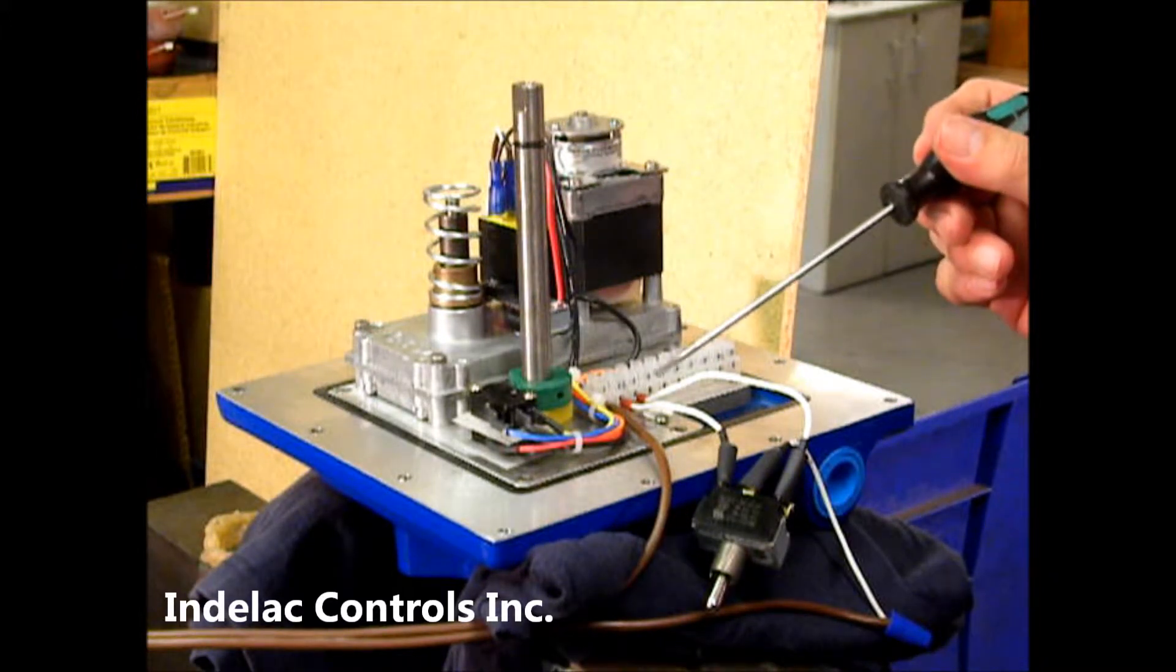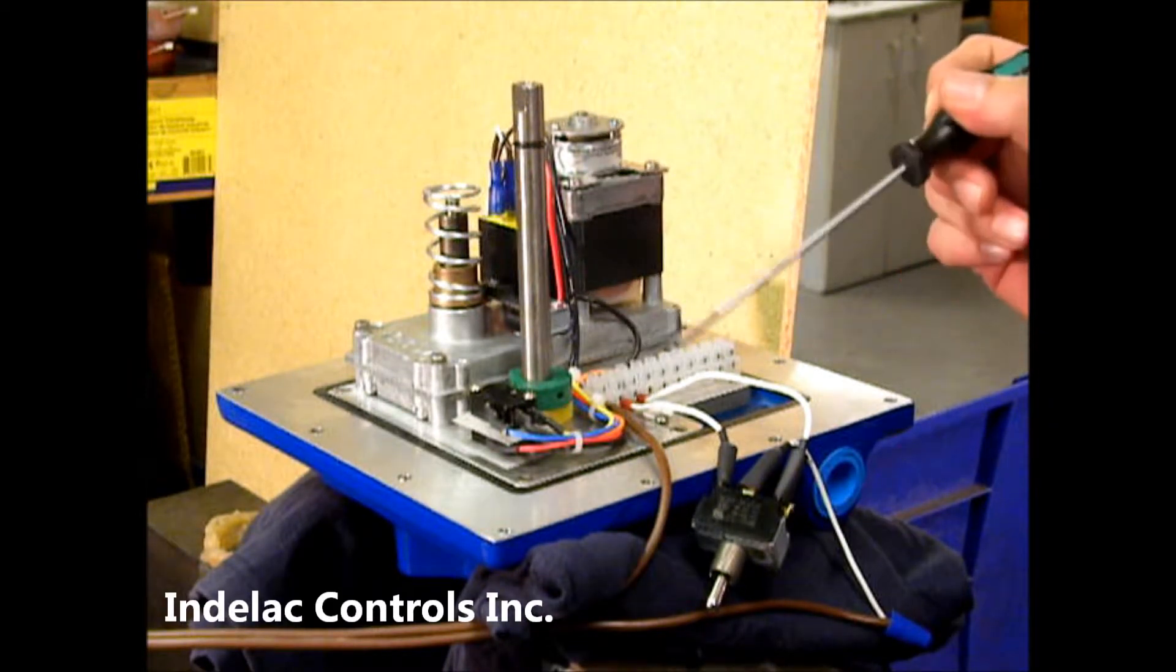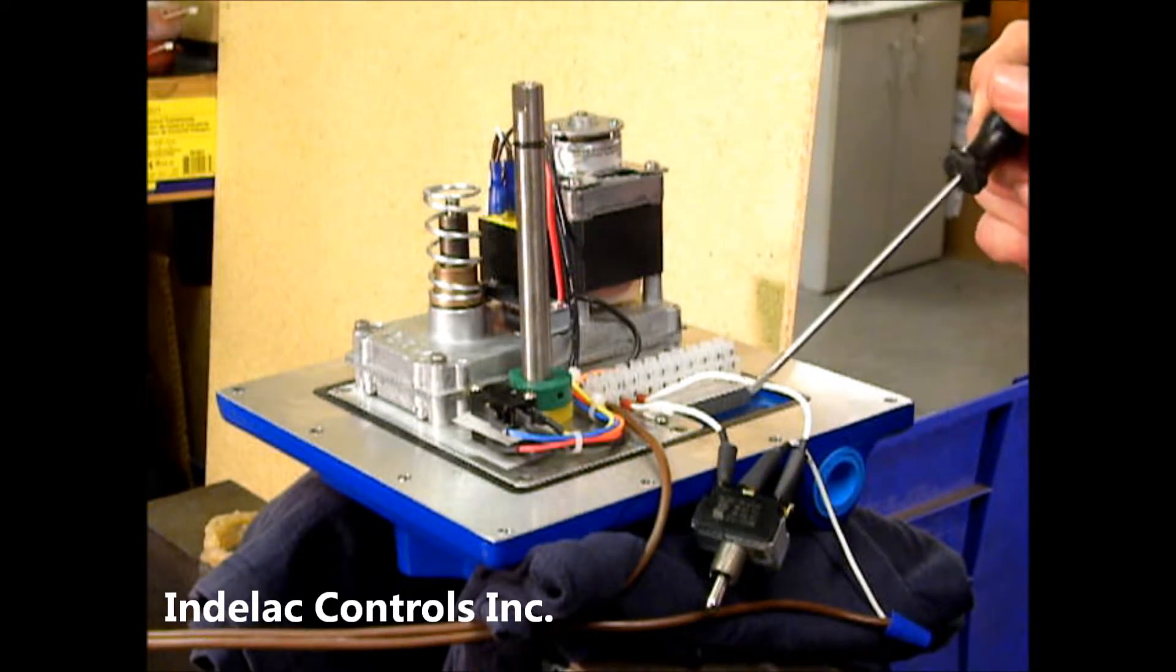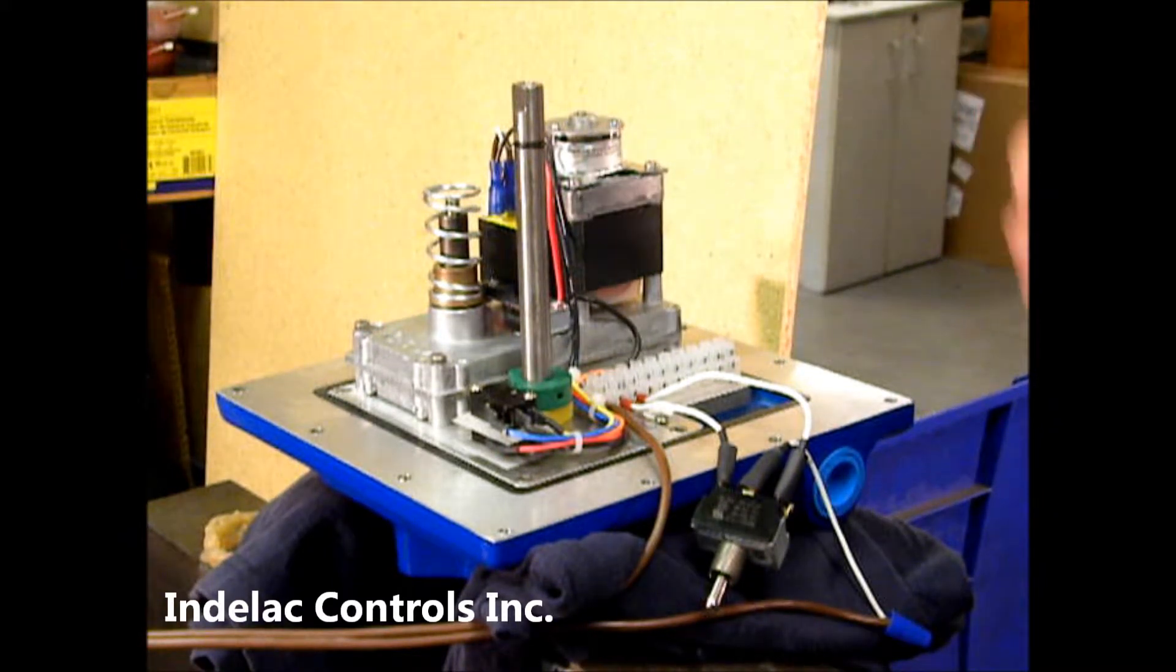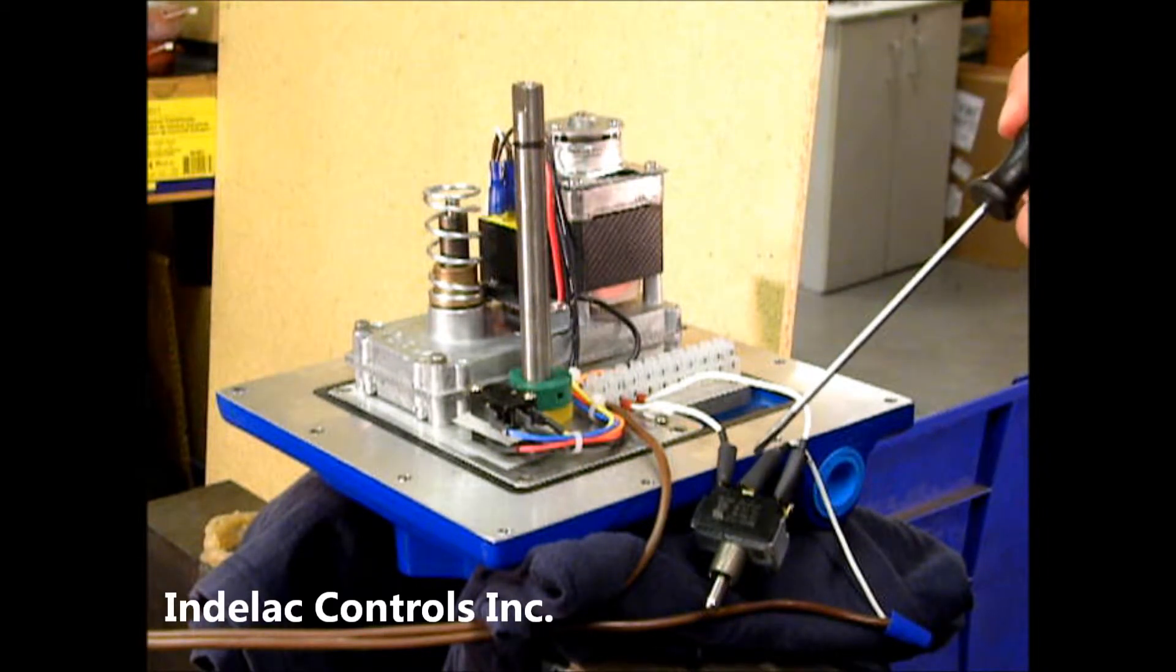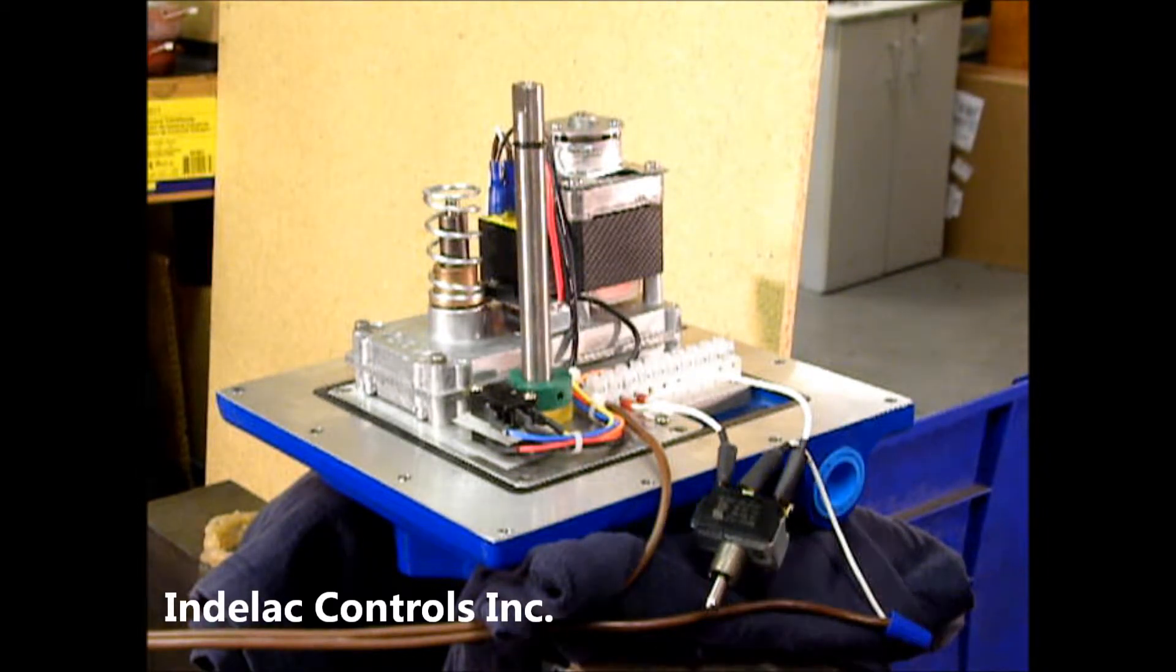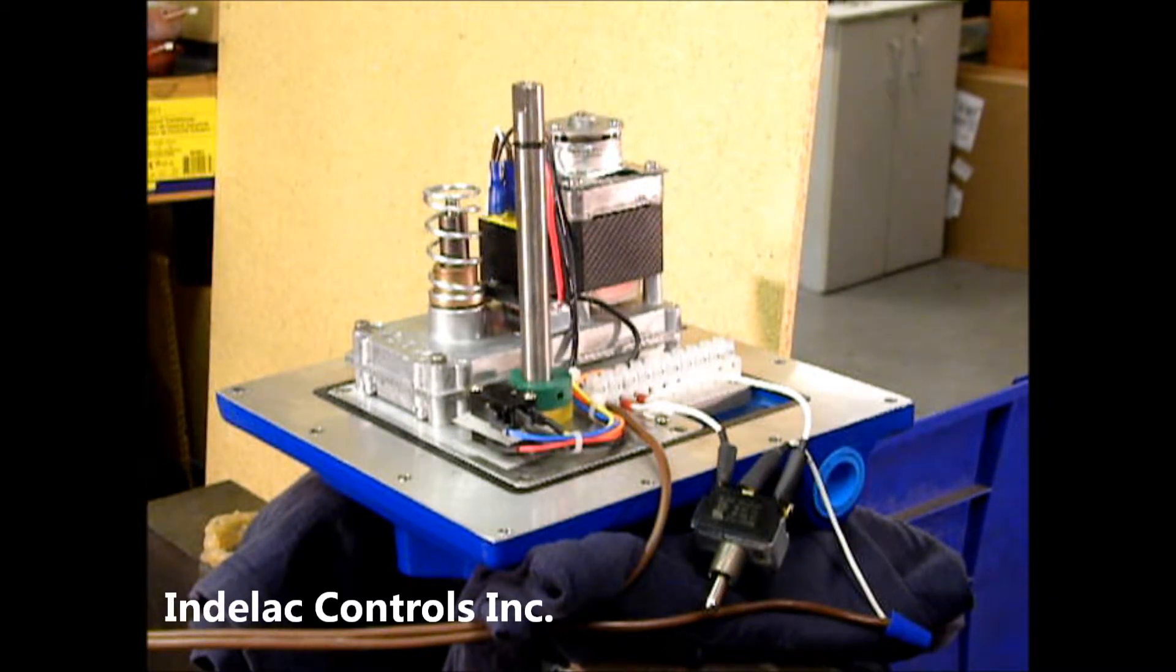This is a two-wire system. You have 120 volts. Your neutral line runs into pin one, and then your hotline is split to go to pins two and three through either a single-pole double-throw contact on a relay or some type of a control switch that is also single-pole double-throw.